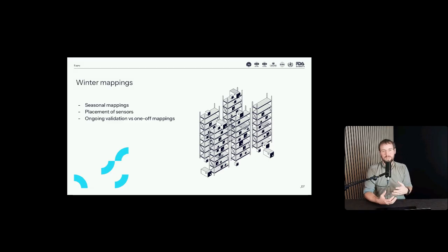It's not something that we'll cover in this webinar, but it's important to note that there is the opportunity to install more sensors than you would normally install during constant monitoring, and thereby actually perform an ongoing validation on a day-to-day basis. Based on that, there are fewer requirements, or less cost associated with having personnel on site to install and retract the loggers, filling in reports and so forth, because you have the constant confirmation that the stability and homogeneity of temperatures is within your requirements. It's a whole other topic, and I think we'll deep dive into that in later webinars. It's definitely an interesting topic.